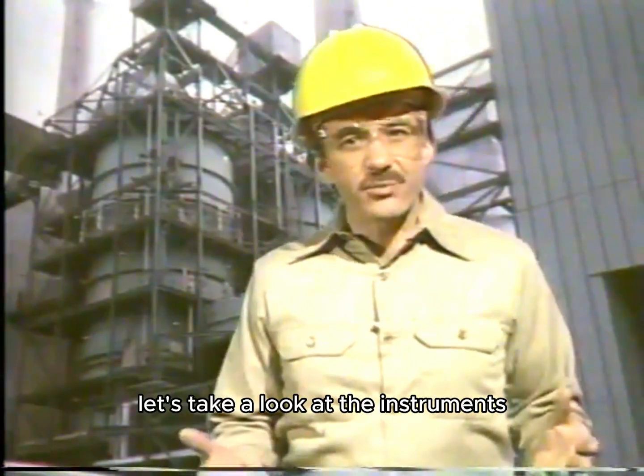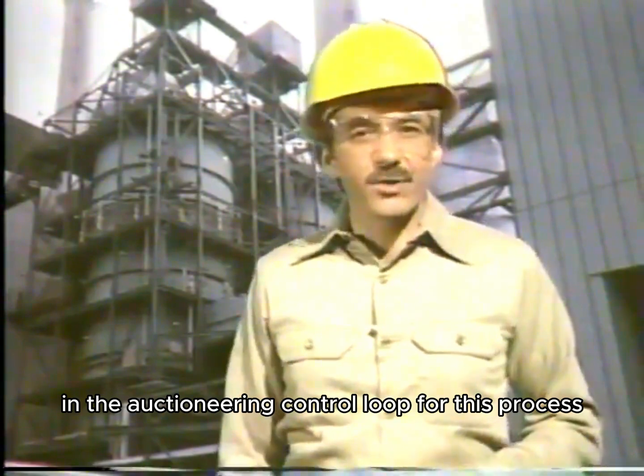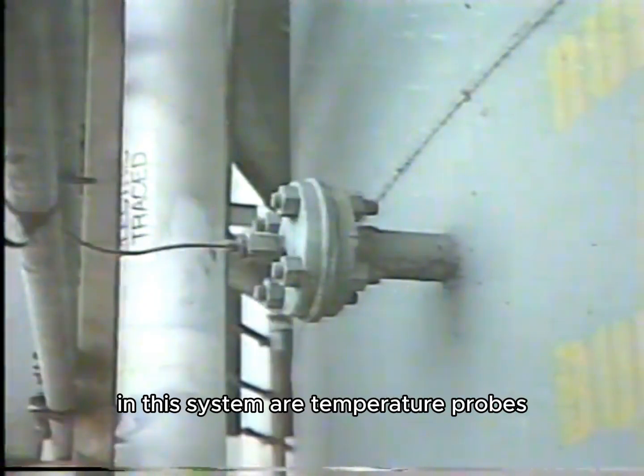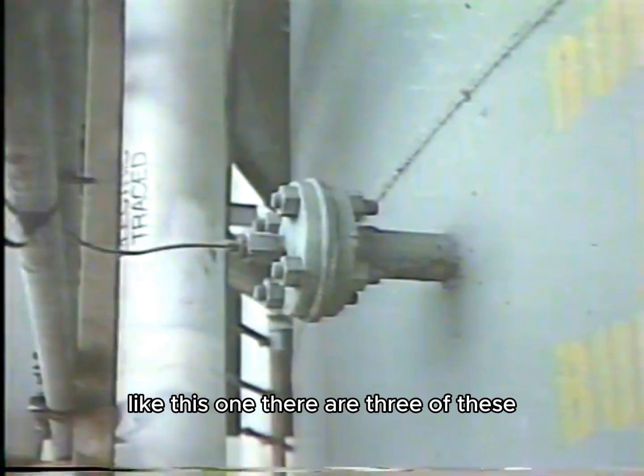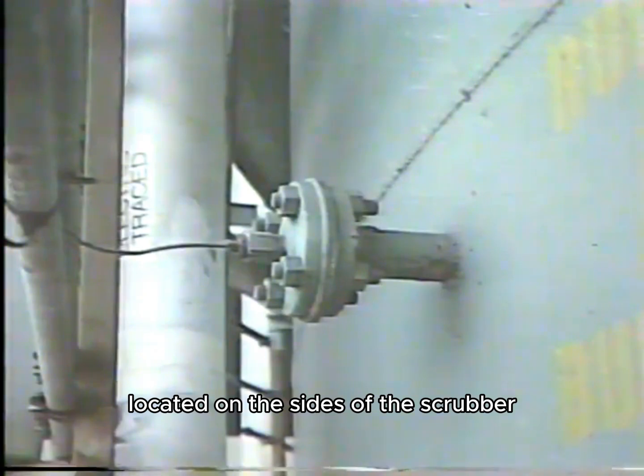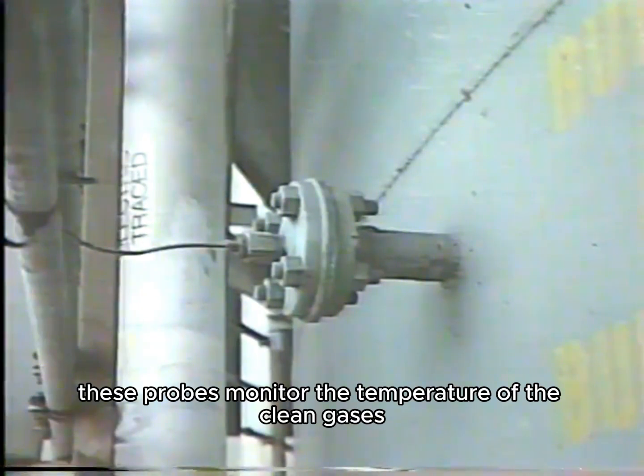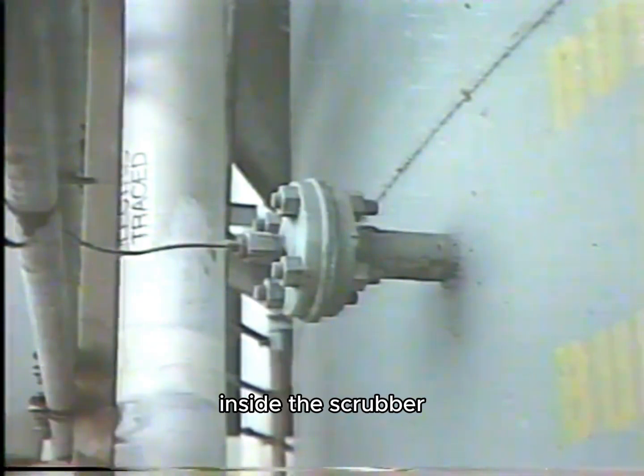Let's take a look at the instruments in the auctioneering control loop for this process. The primary elements for the control loop in this system are temperature probes like this one. There are 3 of these located on the sides of the scrubber. These probes monitor the temperature of the cleaned gases inside the scrubber.